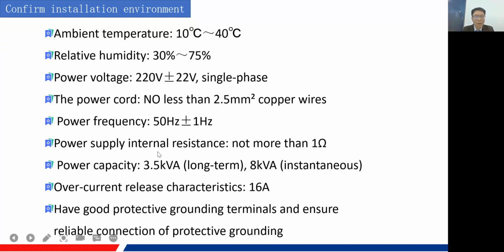And the next one, the power supply internal resistance no more than 1 ohm. The power capacity is 3.5 kilowatt. And the overcurrent release characteristics is 16 ampere. And the last one, we need to take a good protective ground terminal and ensure the reliable connection of the protective grounding. This is for the ground line. We need to have a good ground line.